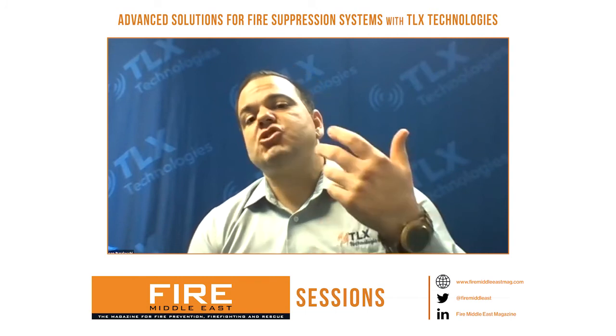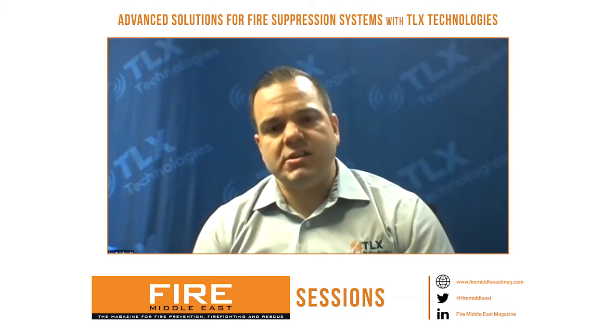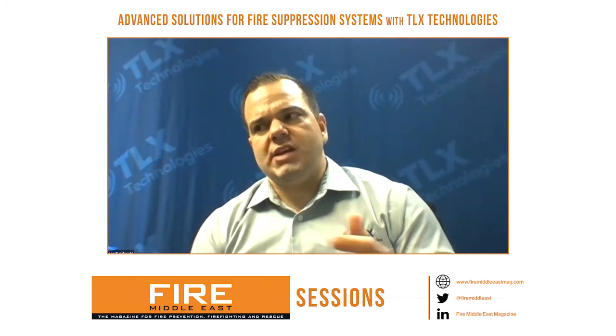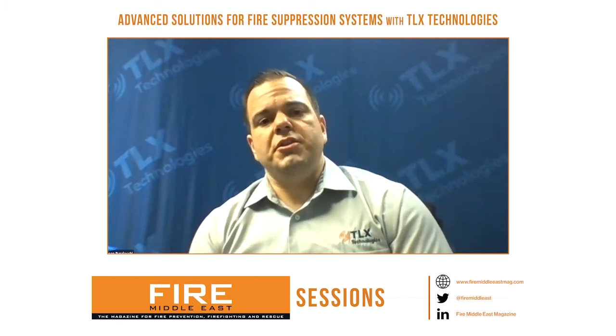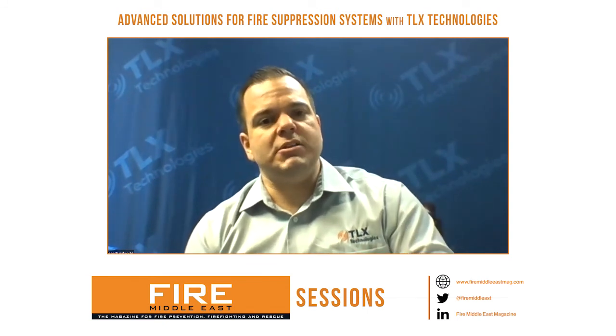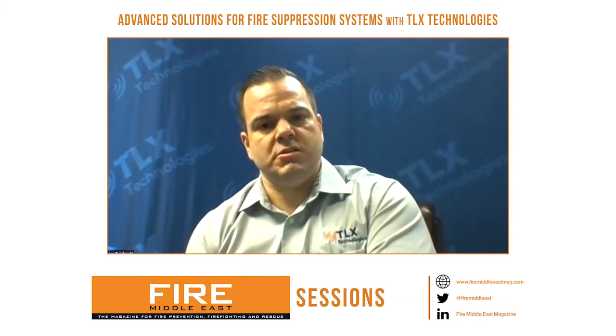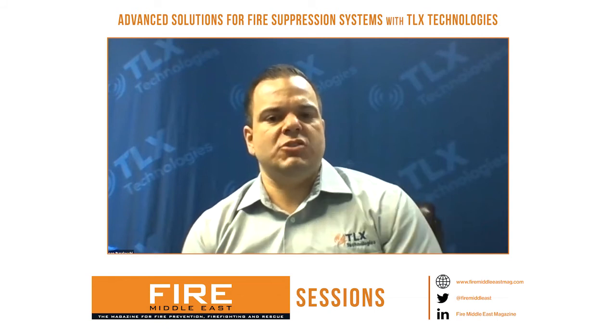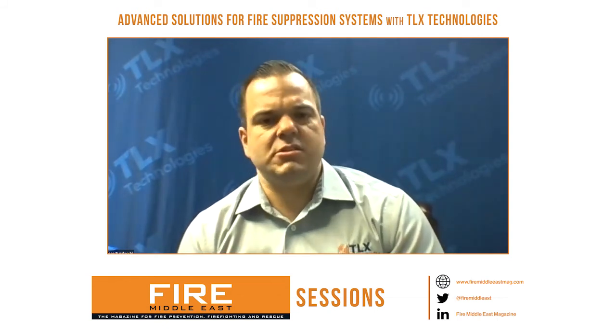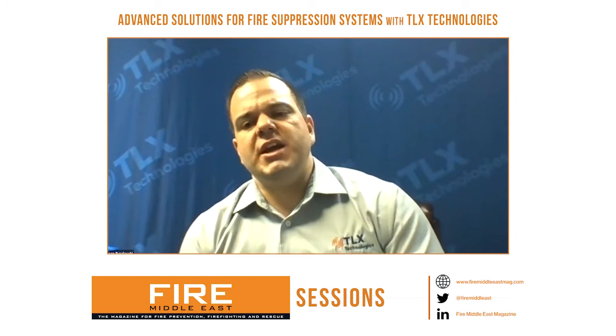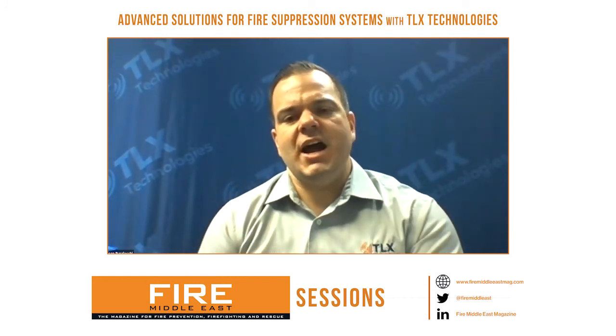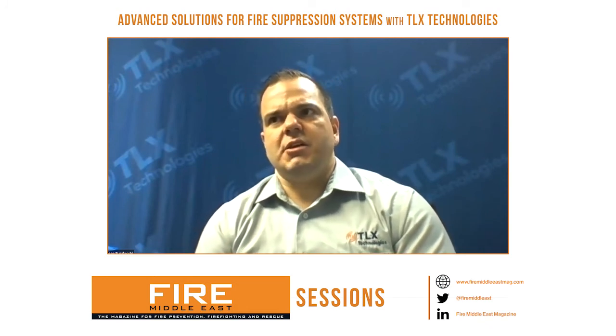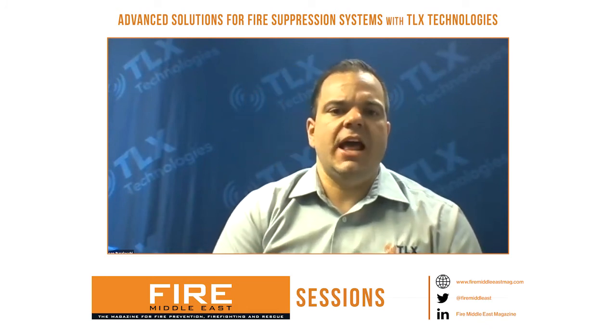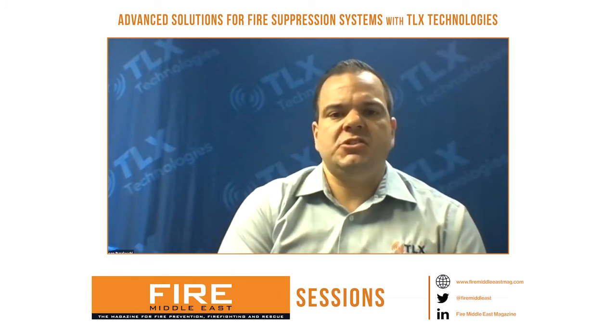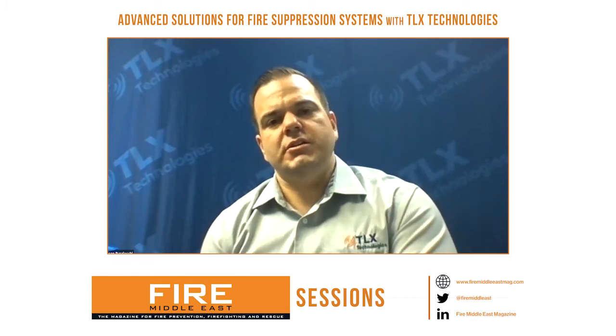I was actually part of the NFPA 13 process, because I was requested to come down with the person who submitted the public comment that NFPA 13 for water systems adopt what's in NFPA 2001 for gas clean agent systems. So the only reason NFPA 12 may not have it yet is that somebody hasn't put in the comment yet, and it hasn't been voted on, or it might still be going through the process at some point in the future.